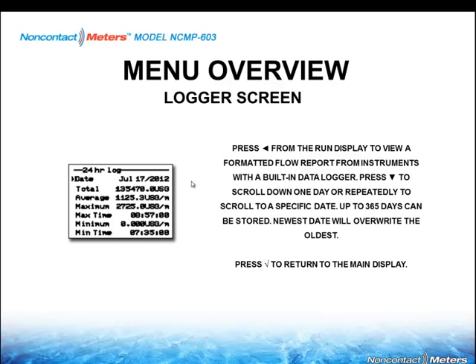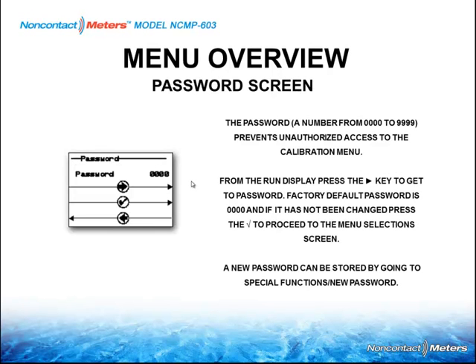A special feature with the logger screen: you can actually scroll down to get daily information up to 365 days, when it's stored in the meter. So, more logger information, kind of interesting for a very economically priced ultrasonic transit time flow meter. And of course, for those people that are concerned, it has a password function. If you want to leave something out in the field and you don't want your neighbors or big brother to come by and change any of your parameters, you can lock it out with a password.